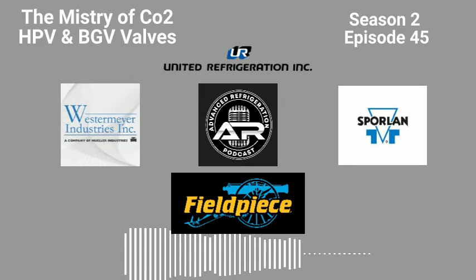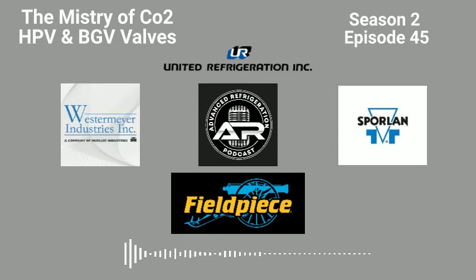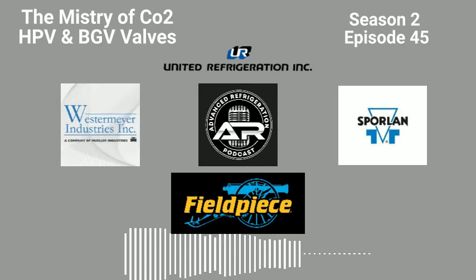Yeah, so the feedback loop is giving you a reference to where that valve actually is. These high pressure valves all have a strainer in them for the most part. I don't know about the Sporlans, I'm assuming they probably do, but the Danfoss for sure have a strainer in them, and they do get dirty. So it is like our deal on startup now.